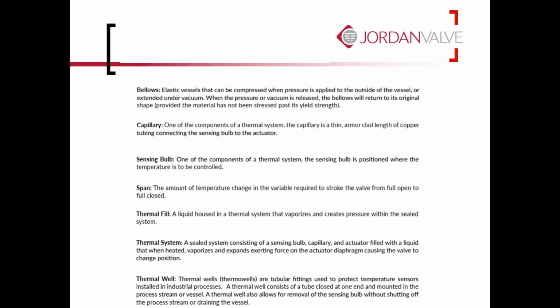Sensing bulb is what's actually touching, or in a thermal well, in whatever it is you're trying to control the temperature of, be it a tank, again, heat exchanger. The sensing bulb is actually going to be in contact with the media that you're trying to control the temperature on. A span, and we'll talk a little bit more about this and do an example later, but the span is very critical. This is the amount of temperature change required to stroke the valve from full open to full close. So if your set point's 150 and you're heating, how cold does it need to get to open the valve all the way in order to get as much steam as possible through it?